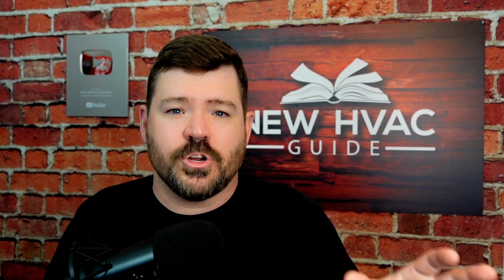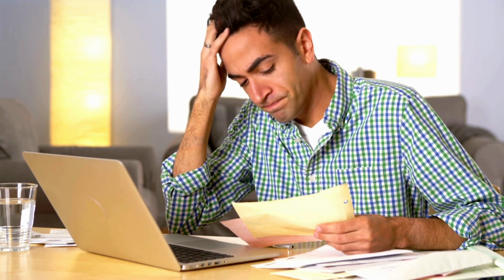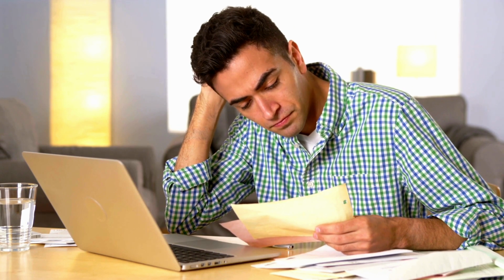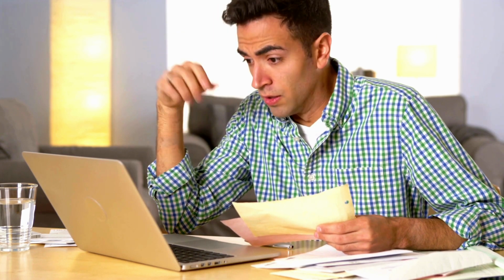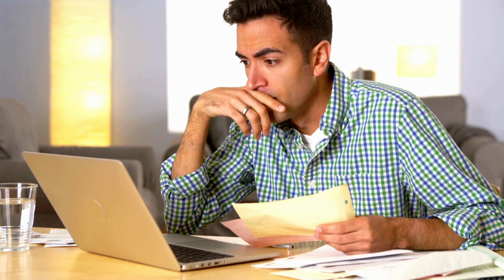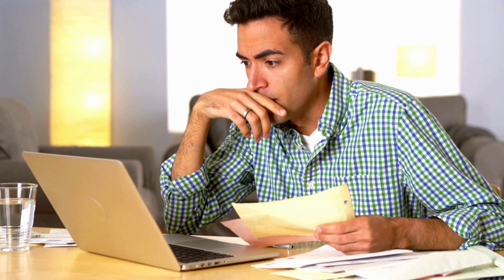They should have looked at the duct sizing to make sure you're not going to have high static problems. And they should have, you know, done all these things. That's when you find out that they didn't, right? After the fact, now that you're having problems. Or maybe you're not even having super big problems, but your electric bill's not as good as you thought it would be, right? You went with this really high-end system, but now your electric bill comes in a month after that, and you thought you'd see a little more savings.